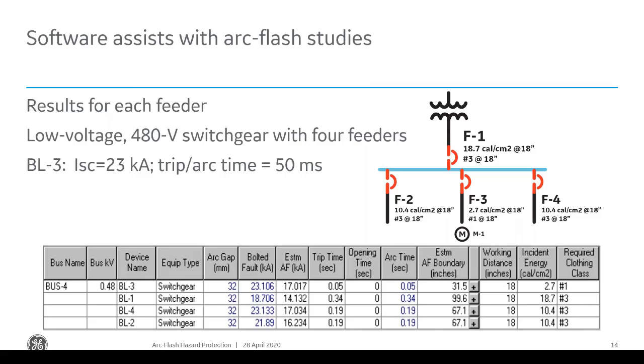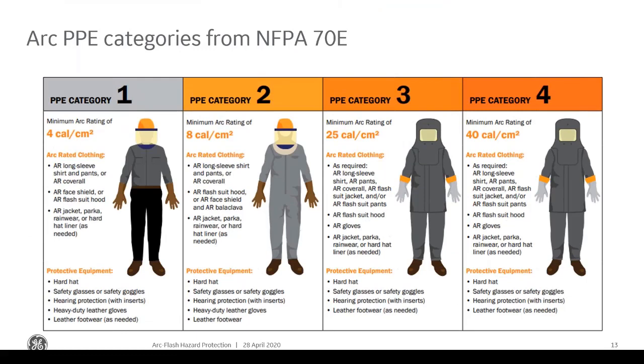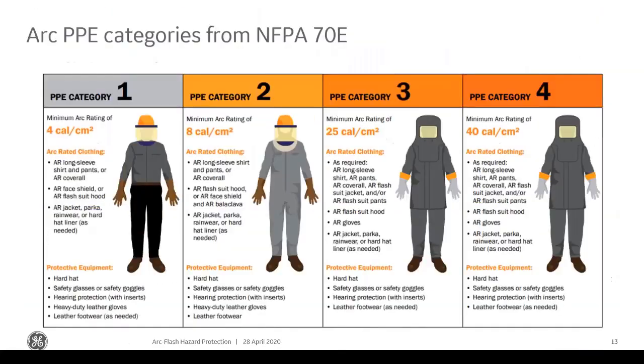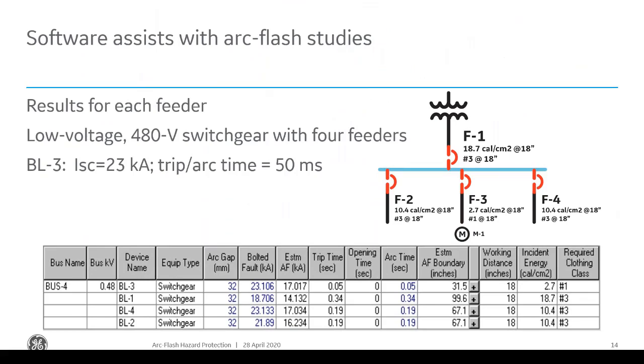Regardless, let's take a look at feeder F3 in this case. Based on the study, it's a 23K short circuit, three-phase fault with about a 50 millisecond arcing time, which gives about 2.7 calories per centimeter squared of arc flash incident energy. And you're talking about going to category 1, so this is pretty much your first level. And then for F2 and F4, it's about 10, so we're talking about going to category level number 3. That will require quite a lot more PPE to be able to go into and work in those arc flash zones.